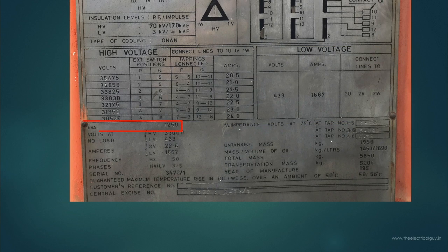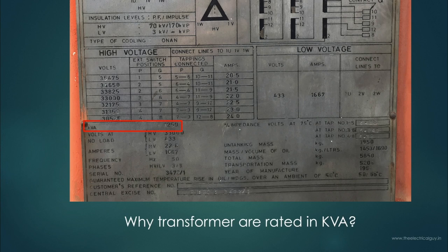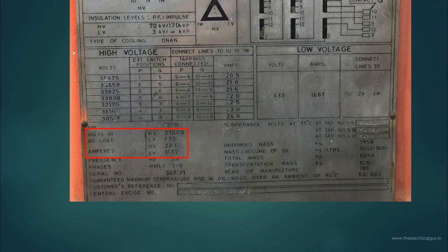Moving on here you can see the KVA rating of the transformer. This transformer is 1250 KVA. By the way if you would like to know why transformers are rated in KVA only you can watch my video on that. You will get link for that video down in the description. Next thing is voltage and amperes. Here you can see high voltage is 33 KV, low voltage is 433, high voltage ampere is 22 amps and the low voltage is 1667 ampere.